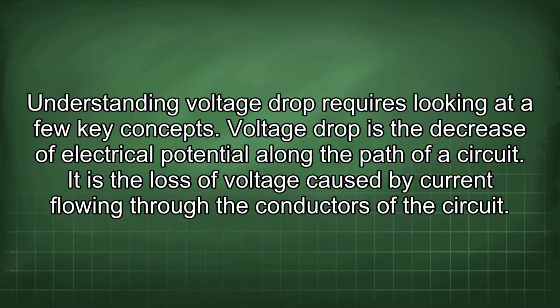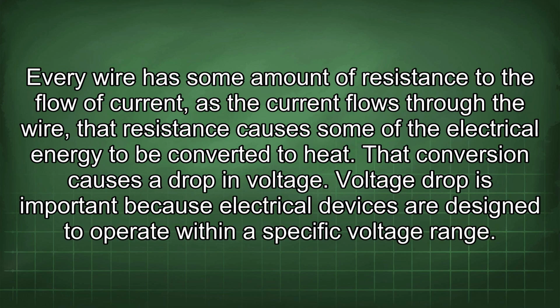Understanding voltage drop requires looking at a few key concepts. Voltage drop is the decrease of electrical potential along the path of a circuit. It is the loss of voltage caused by current flowing through the conductors of the circuit. Every wire has some amount of resistance to the flow of current. As the current flows through the wire, that resistance causes some of the electrical energy to be converted to heat. That conversion causes a drop in voltage.